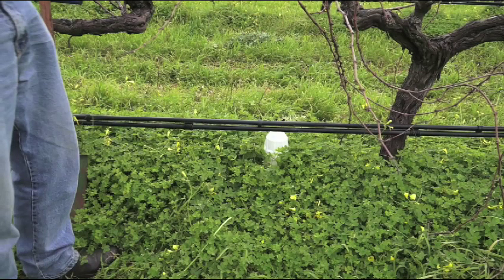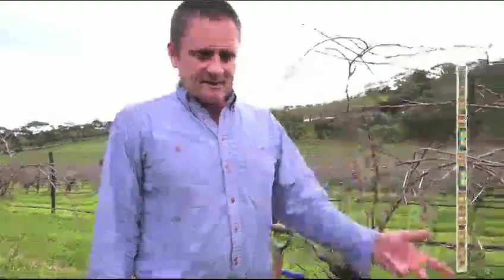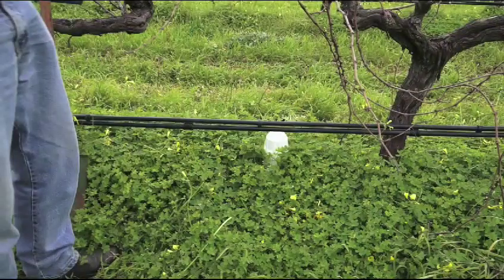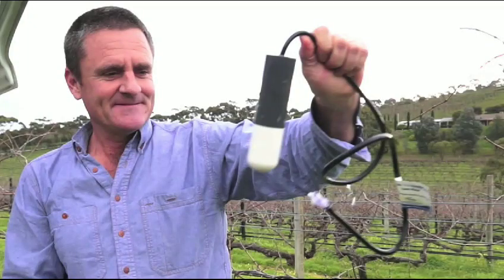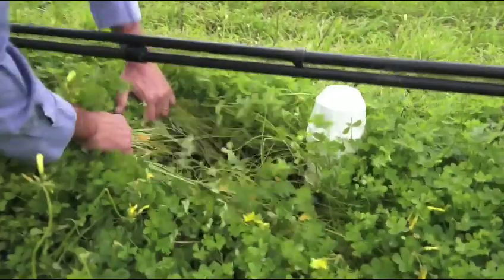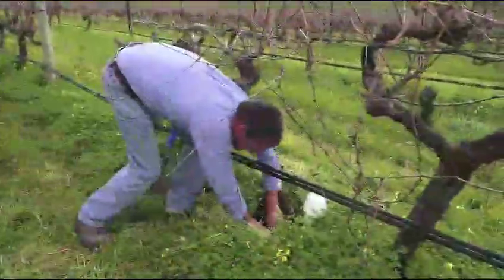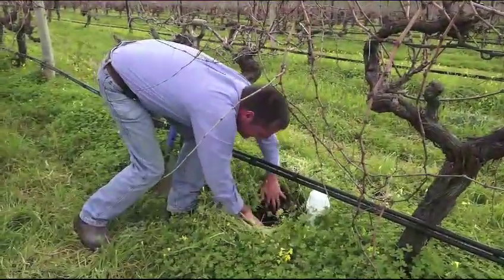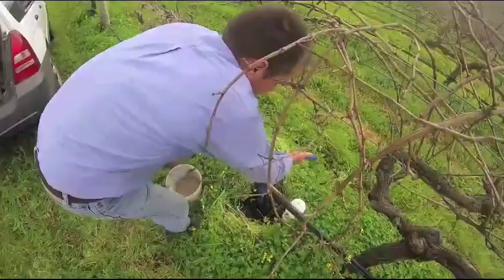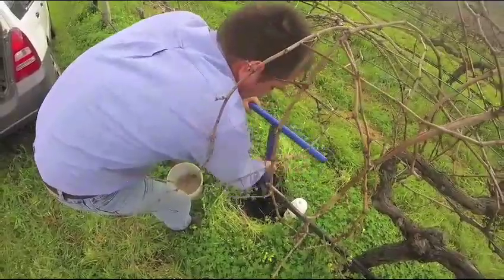This is an existing SENTEK probe. It's a 5 sensor probe. Moisture, tri-scan at 30, then another moisture at 50, tri-scan at 70, and another moisture at 1 metre. I'm going to use the Solu sampler to calibrate the tri-scan sensor on the probe. And we're going to put that Solu sampler at 30 centimetres so we can calibrate the tri-scan sensor on the probe. And this is going to be the location of the Solu sampler. This is being installed at 30 centimetres.